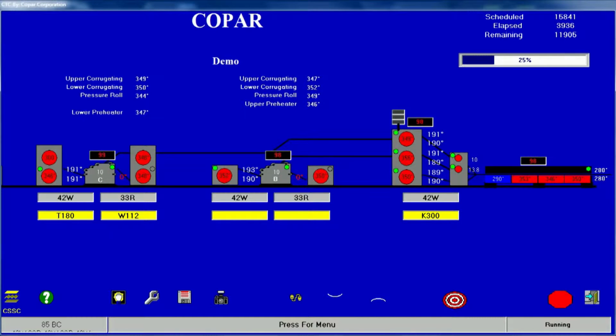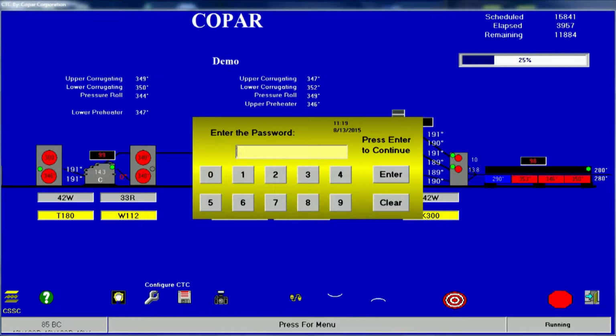Next, we will look at the Copar calibration screens. First, navigate to the blue CTC Quality Master screen. Next, press the wrench icon on the bottom of the screen to open the configuration. When prompted, enter your maintenance password and press Enter.